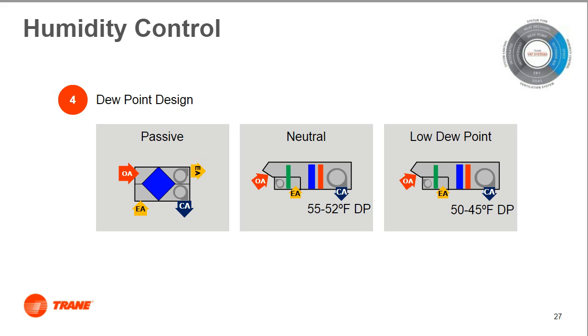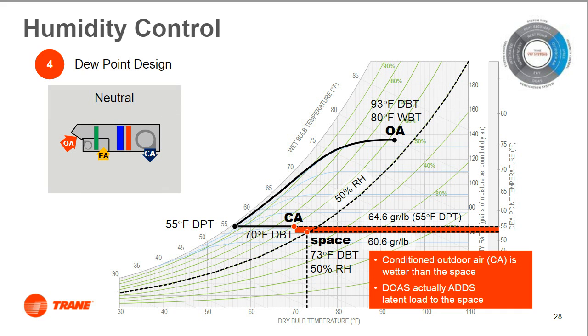For example, right now we're analyzing whether or not the neutral method of air delivery should be used in this particular case. But we start off with an outside air condition of 93 degrees dry bulb, 80 degrees wet bulb, pretty moisture-laden air. Indoors, we have a space temperature of 73 degrees dry bulb and a relative humidity of 50%.